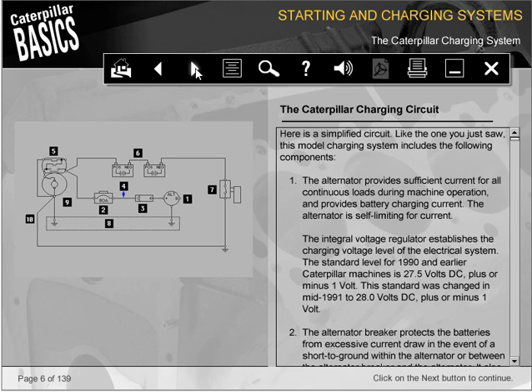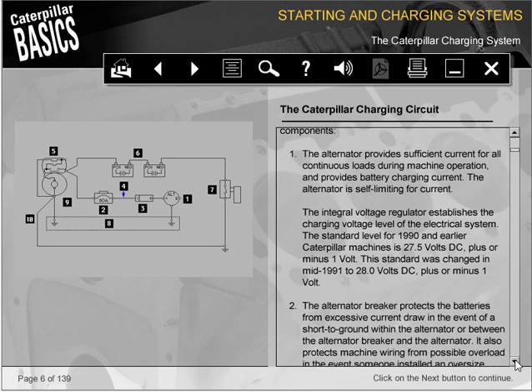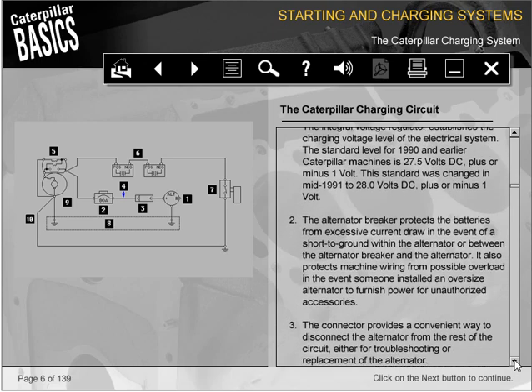1. The alternator provides sufficient current for all continuous loads during machine operation and provides battery charging current. The alternator is self-limiting for current. The integral voltage regulator establishes the charging voltage level of the electrical system. The standard level for 1990 and earlier Caterpillar machines is 27.5 volts DC, plus or minus 1 volt. This standard was changed in mid-1991 to 28.0 volts DC, plus or minus 1 volt.